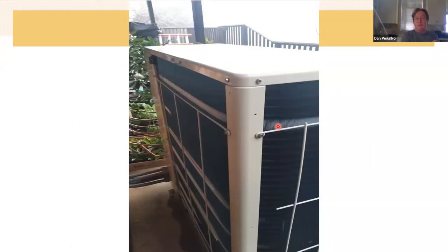This is a photo of, I normally do this as a question, but we're doing it for time. In any case, this is a variable capacity heat pump. I usually make people guess a bunch to tell me why this is happening, but I'm worried I won't have time. So what you're seeing right here is frost. The frost is developing on the outside unit because the unit is absorbing heat from the outside air. The refrigerant is boiling in that coil, but it's boiling at like 20 degrees, right? And it's maybe 45 degrees outside. So it's so cold at its boiling point where it's absorbing heat that the moisture in the outside air is condensing and then freezing on the coil. And so you'll see heat pumps do this, they get frosty.